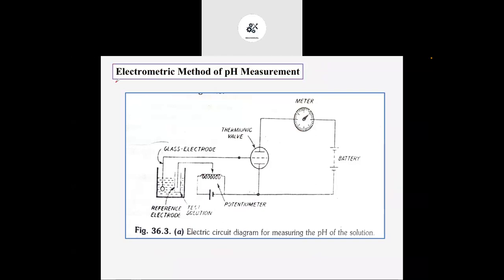So, measurement of the pH value. This is one of the methods which we use to measure the pH value of feed water. That is the electrometric method of pH measurement. Okay, this circuit you will see here contains the circuit which will measure the pH value.